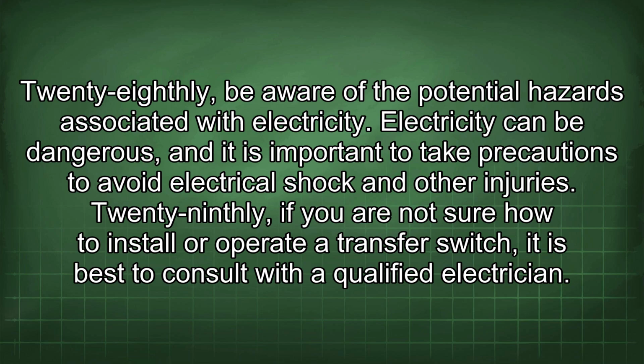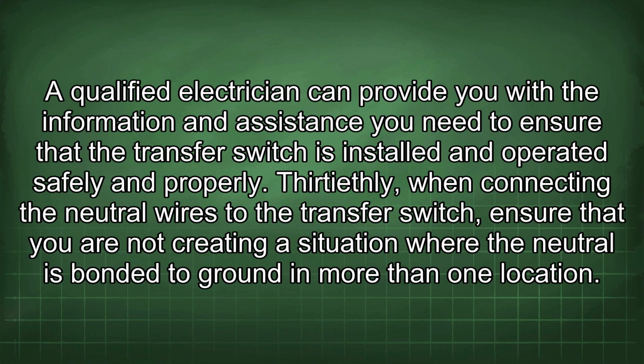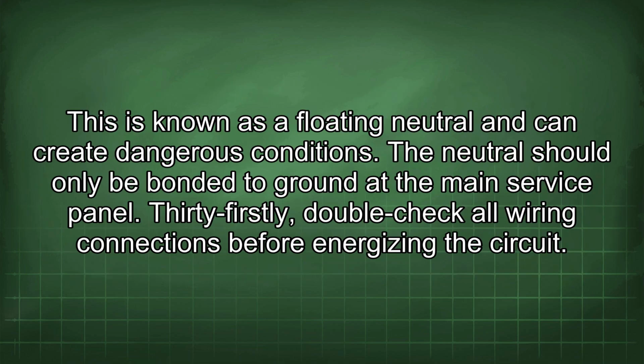29thly, if you are not sure how to install or operate a transfer switch, it is best to consult with a qualified electrician. A qualified electrician can provide you with the information and assistance you need to ensure that the transfer switch is installed and operated safely and properly. 30thly, when connecting the neutral wires to the transfer switch, ensure that you are not creating a situation where the neutral is bonded to ground in more than one location. This is known as a floating neutral and can create dangerous conditions. The neutral should only be bonded to ground at the main service panel.